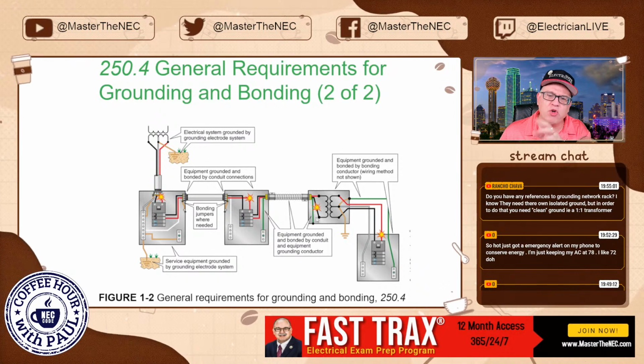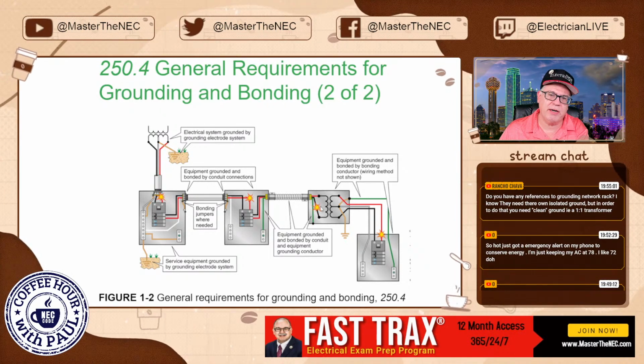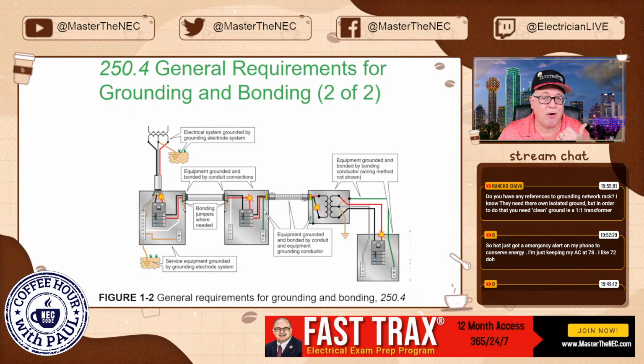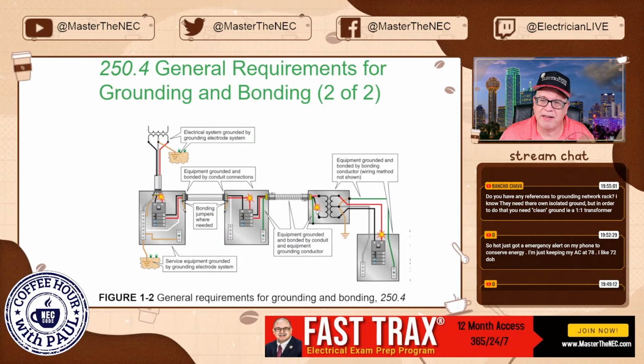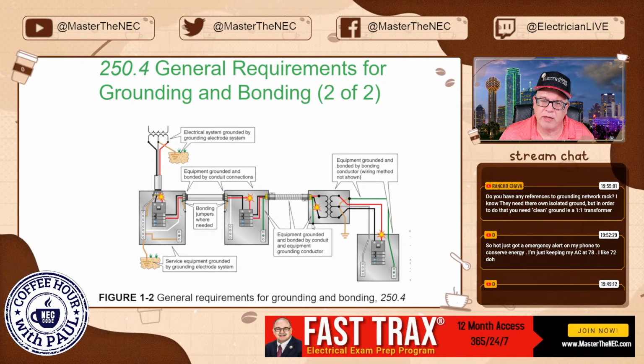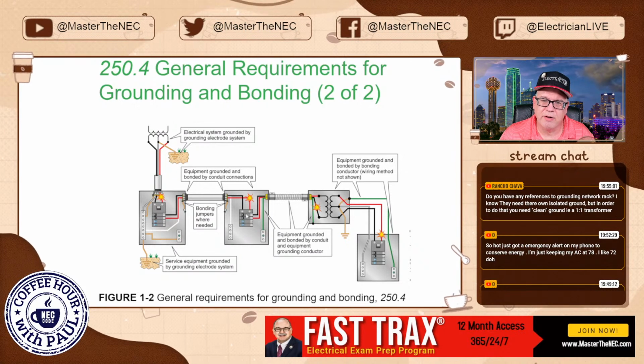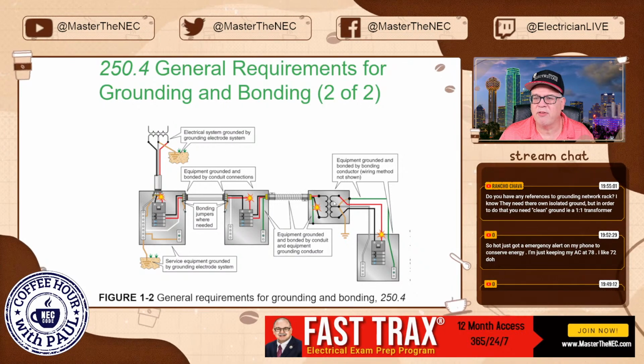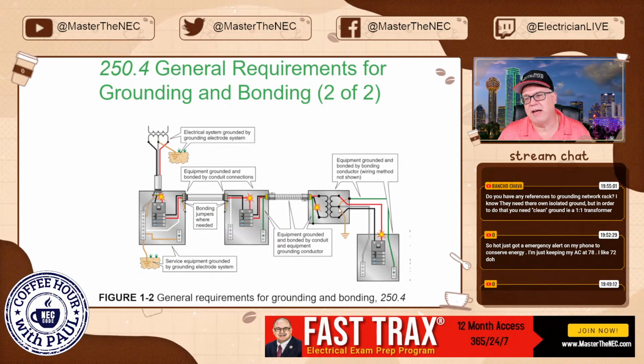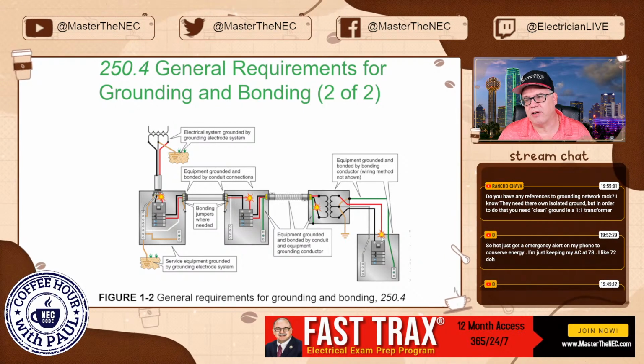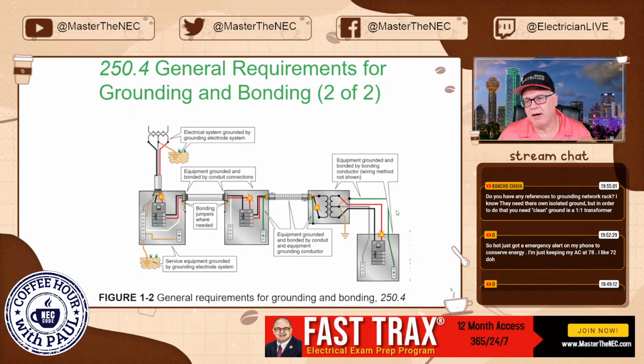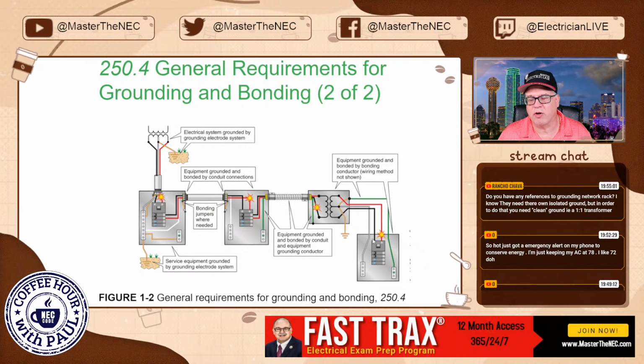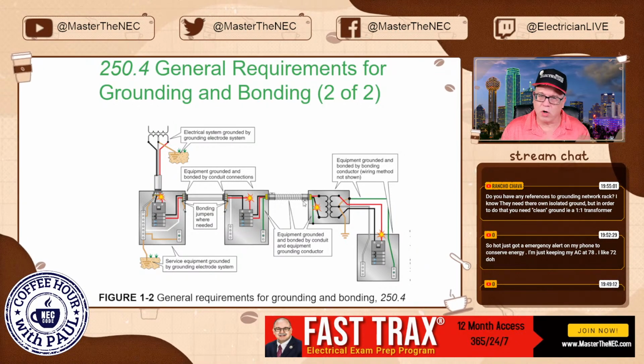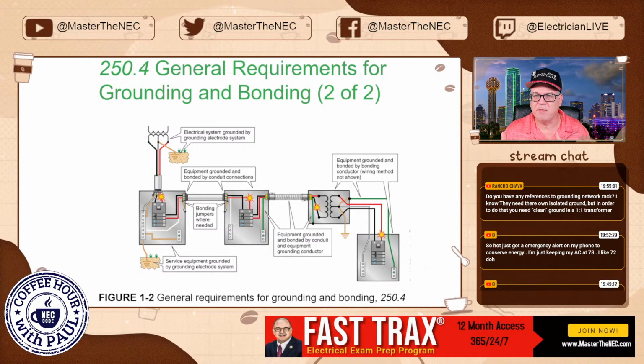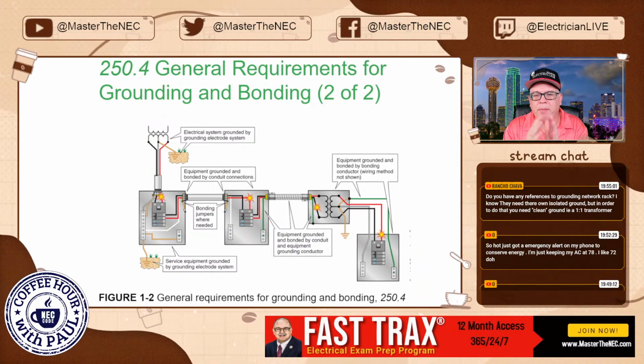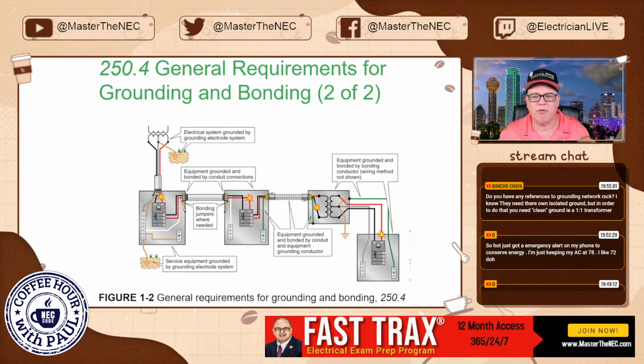And here, even though you wouldn't have a neutral on the primary, you still have to take an equipment ground. You've got to clear an overcurrent device, right? So there's a fault right here, it gets on the equipment ground, comes back here and clears the overcurrent device. And then you have the secondary, and you have a fault right here. It all comes back to the source and allows the overcurrent device to trip here. The whole system works. And we're going to look at the pieces. But proper bonding, proper grounding, doing everything properly.